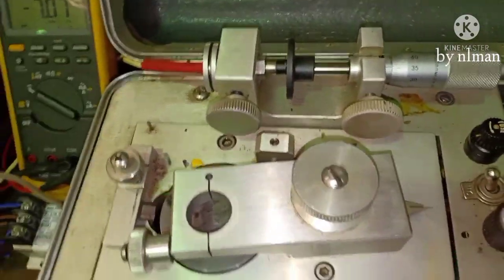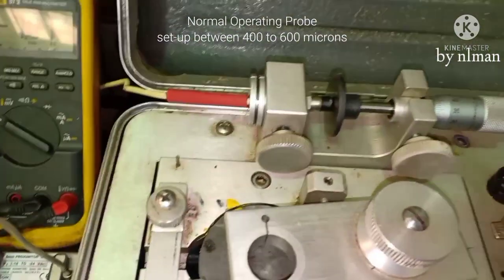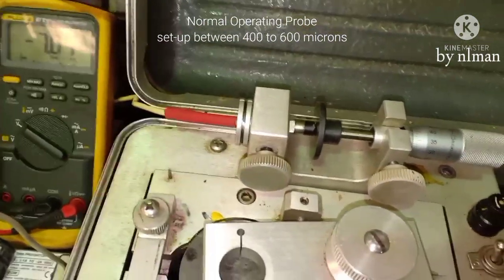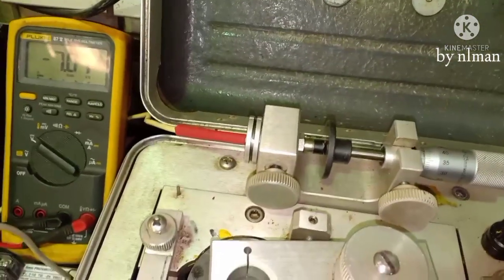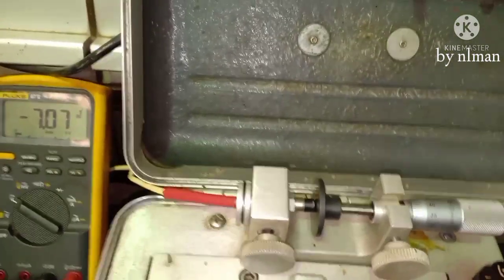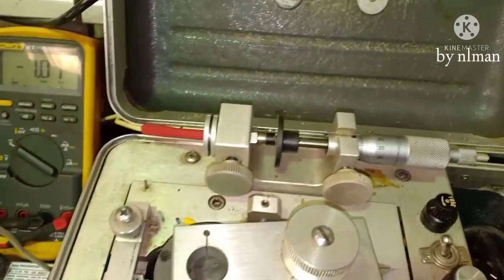So this is how to check the probe. The output of that one should be linear, and normally the probe is set between 400 to 600 microns, okay guys.